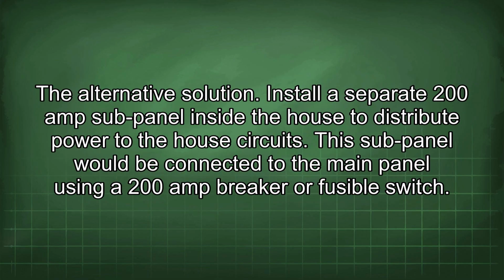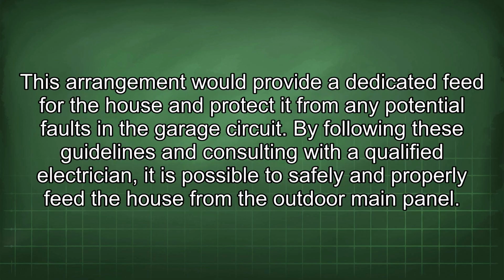The alternative solution. Install a separate 200 amp sub-panel inside the house to distribute power to the house circuits. This sub-panel would be connected to the main panel using a 200 amp breaker or fusible switch. This arrangement would provide a dedicated feed for the house and protect it from any potential faults in the garage circuit. By following these guidelines and consulting with a qualified electrician, it is possible to safely and properly feed the house from the outdoor main panel.